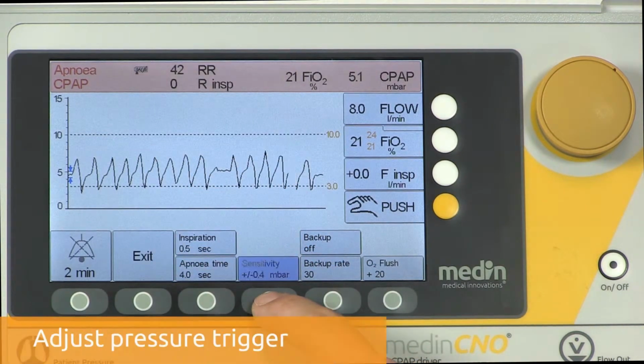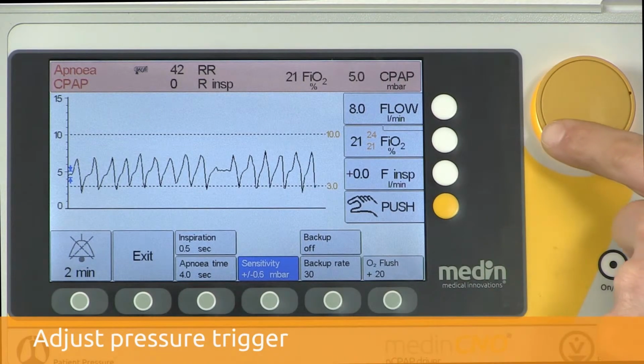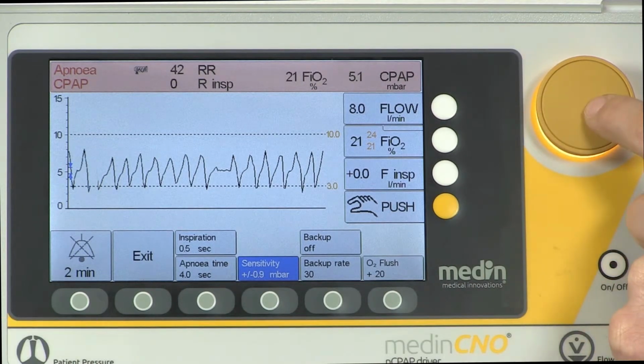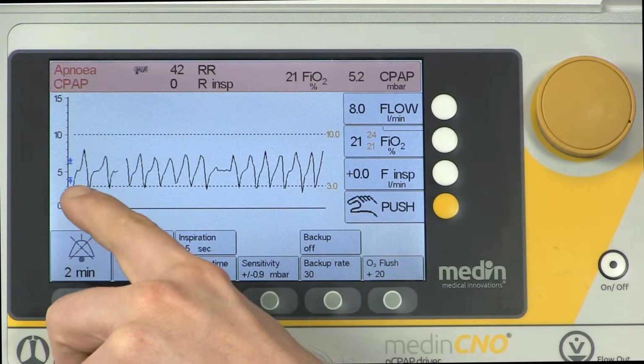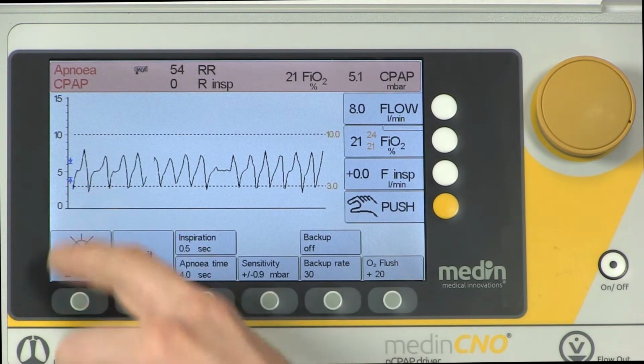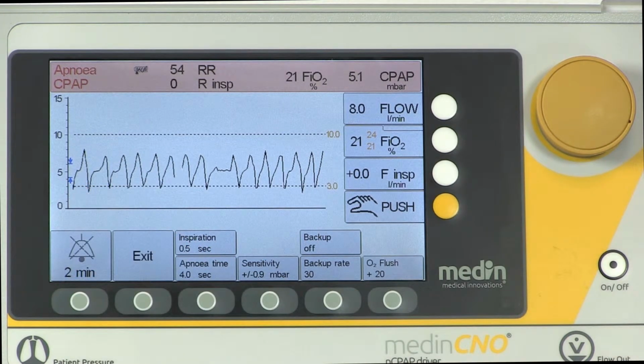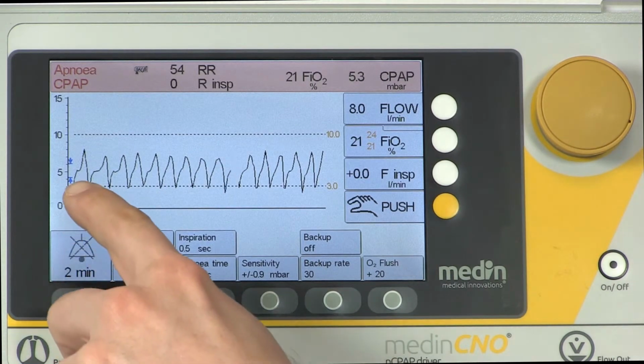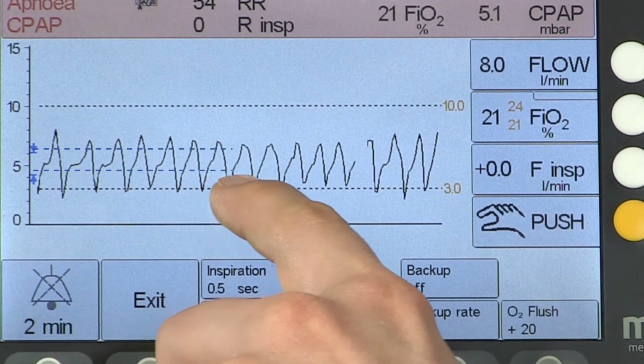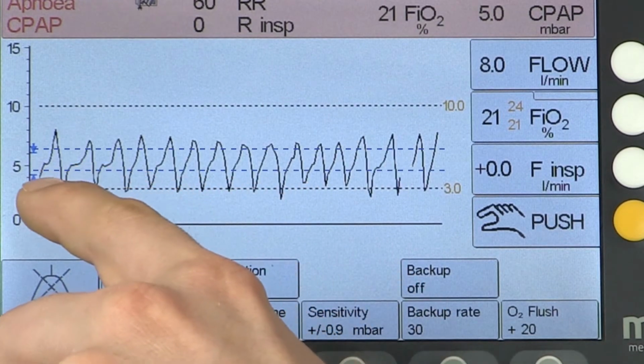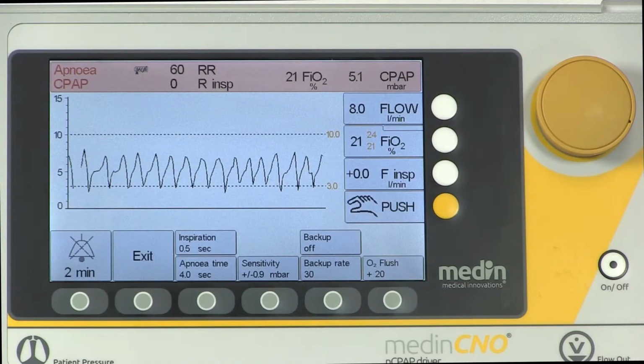The adjustable sensitivity of the trigger pressure enables you to react properly to the baby's spontaneous breathing activity. The pressure trigger is set correctly when the pressure fluctuations during spontaneous breathing go beyond the trigger thresholds, which are indicated with blue arrows. With this innovative pressure trigger, the medinCNO picks up both central and obstructive apneas.